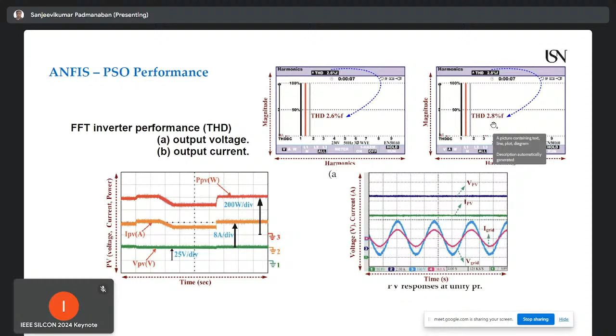You can see how regulation is achieved in real time for the photovoltaic power, current, and voltages. Despite these perturbations, high profile voltage is maintained from the induction drive as well as the current, which remains unity in nature, and stable power from the photovoltaic is regulated as input to the inverters. This is very important - we always try to keep reduced total harmonic distortion in voltage and current, around 2.6% and 2.8%, well below the 5% IEEE standard.